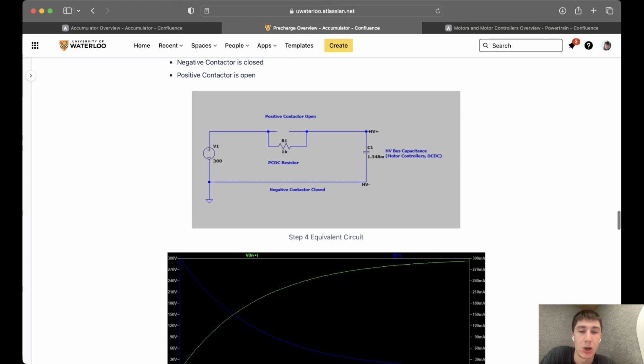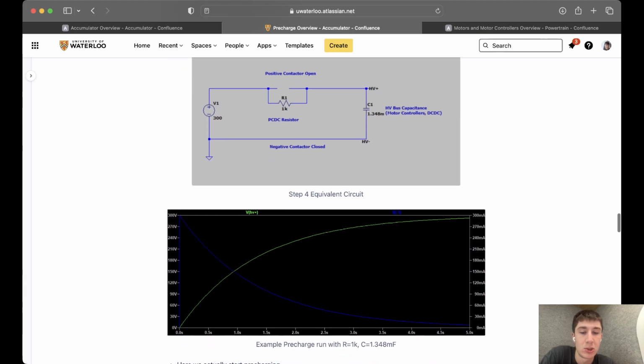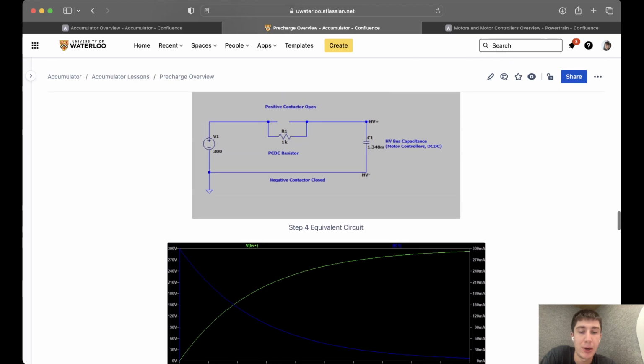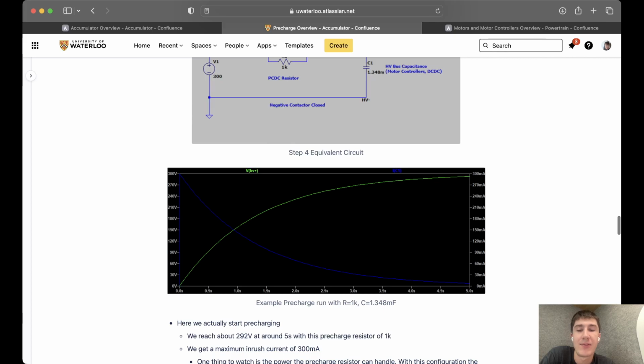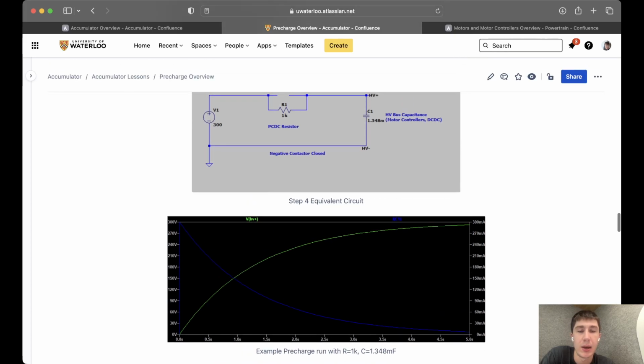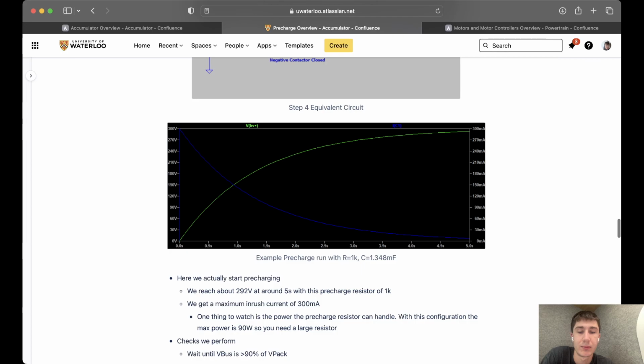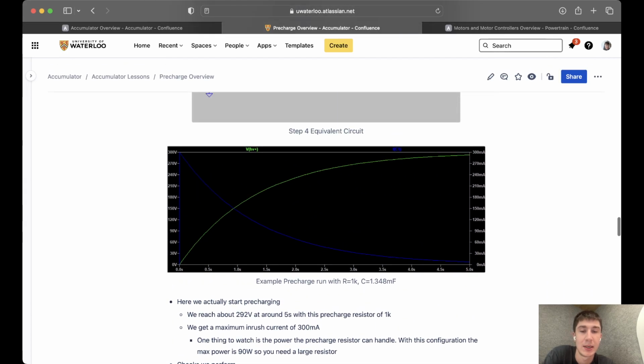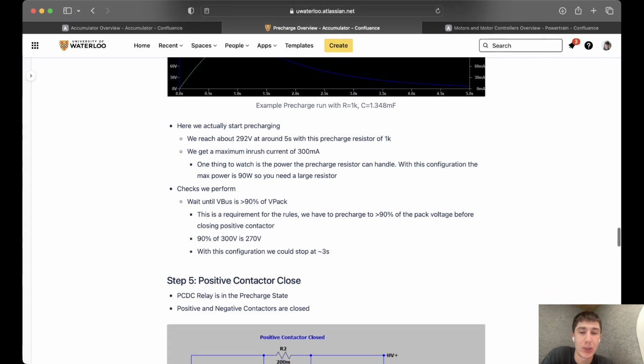And effectively what we've created is an RC filter, an RC charging circuit. So I ran an LTspice simulation using these simple parameters, and this is the precharge system we get. We have a little bit of a current spike here because instantaneously we're applying voltage to the capacitor, though not a tremendous amount as we have our current limiting resistor. So we have a little spike of current and then it decays over time as the capacitor charges up. And we also have our voltage on our high voltage bus steadily increasing. So we don't surpass 300 milliamps, which is very good. And we slowly precharge our high voltage bus. And along the way, we perform checks, and we go on to the next step when our bus voltage is greater than 90% of our battery voltage.